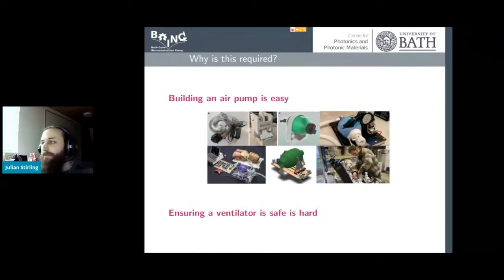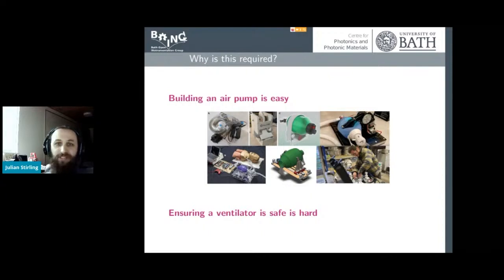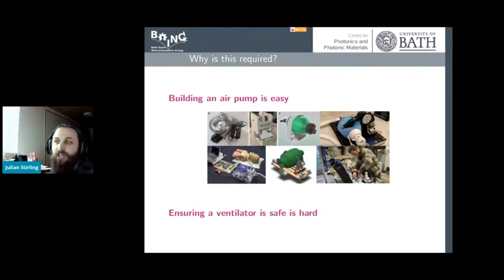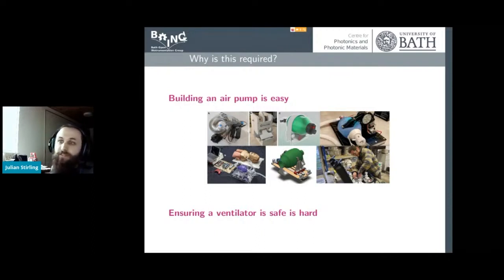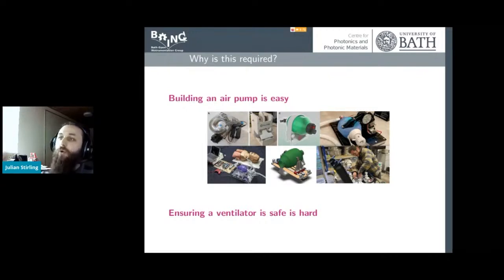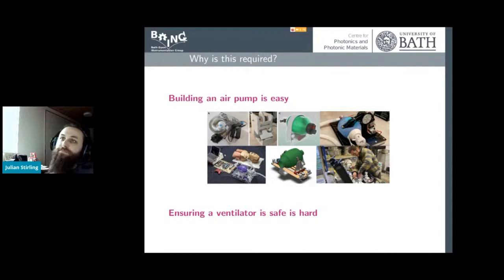Why is all this required? It sounds onerous, but the important point that came up during the pandemic is that building an air pump is pretty easy. Most open source ventilators were much more sophisticated than that, but you have to ensure your ventilator is safe to go on a patient and safe to stay on a patient for maybe weeks at a time, and then carefully take them off as they return to normal breathing. The way they mitigate risk for medical devices is by making sure you've documented every piece of thinking — for instance, in your ventilator, you decided to put a valve here rather than there. Why? That should be recorded so if it ever goes wrong, they can go back and check that you did your due diligence on the design.